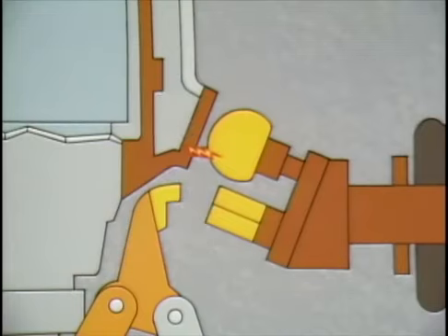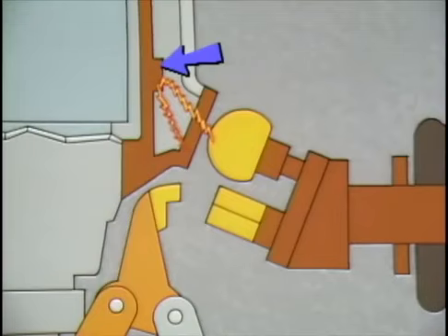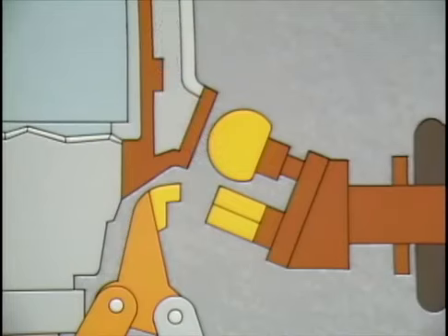and ring. The air blast continues to elongate the arc and forces it off the arcing ring into the arc chute to an arcing electrode. By this time, the air blast has stretched and cooled the arc enough so that it extinguishes at a current zero and the circuit is opened.